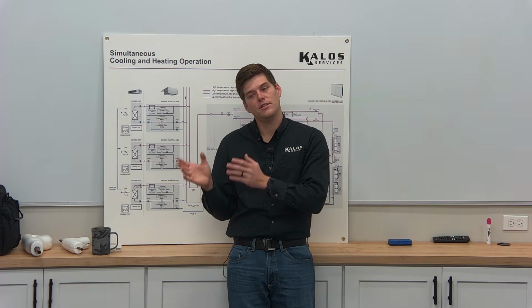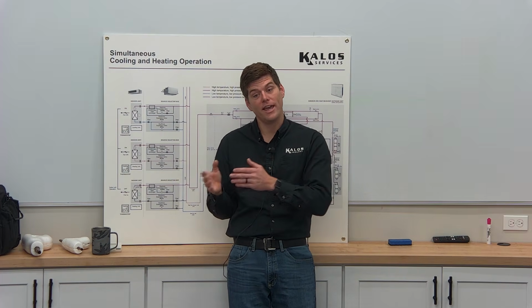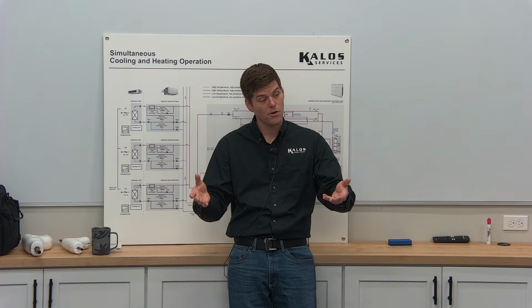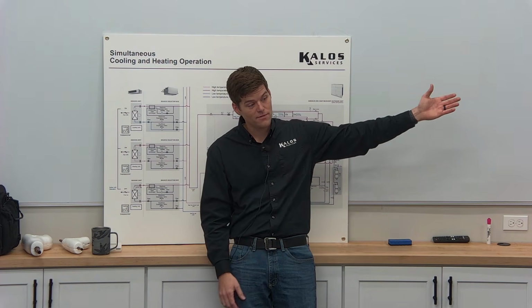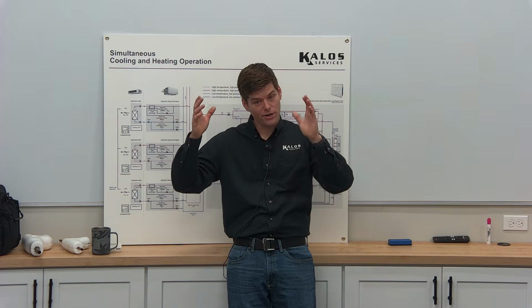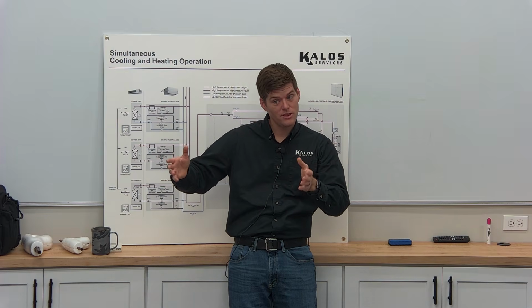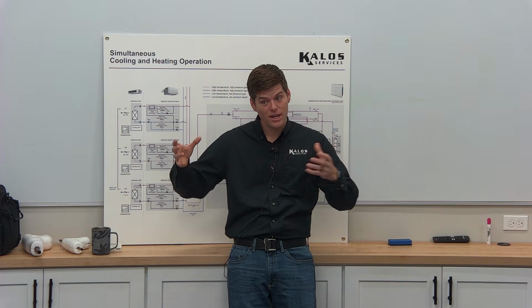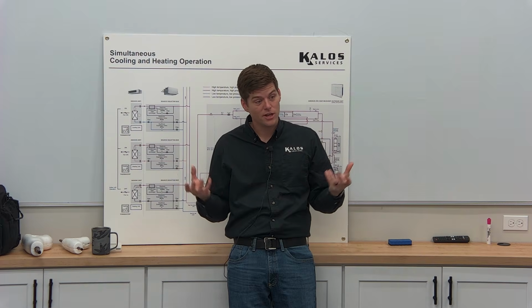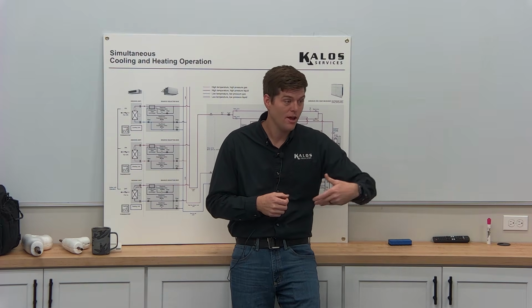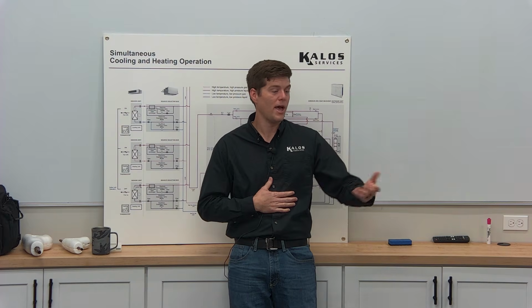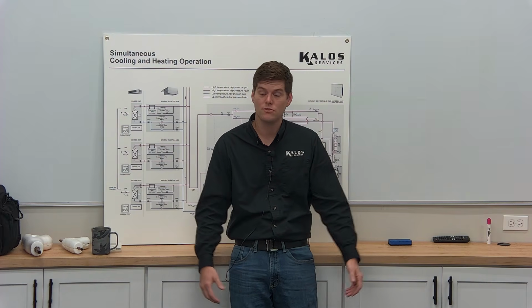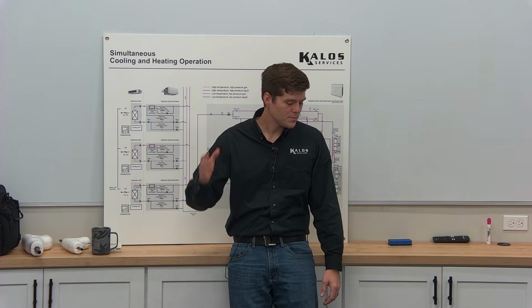VRF does it differently. They're actually like a VFD drive with a fan motor where they're taking AC voltage, converting it to DC voltage, and taking that DC voltage and charging capacitors like you would in an outdoor unit trying to start a fan motor in a residential system, or a capacitor that's supposed to start a compressor, right? A scroll compressor.